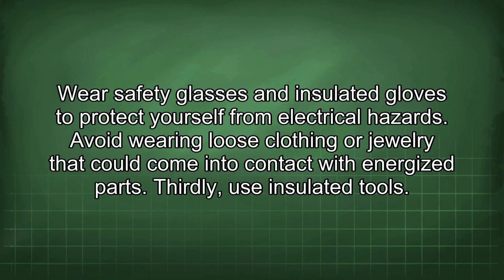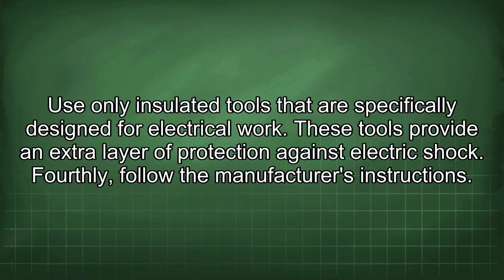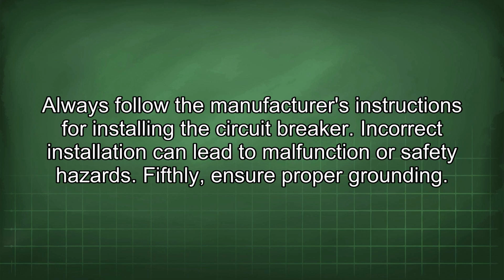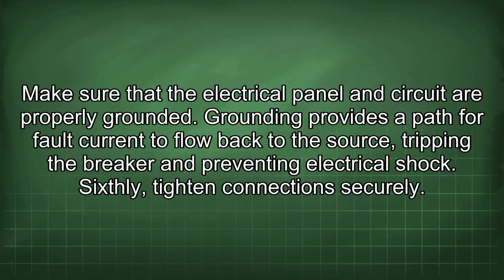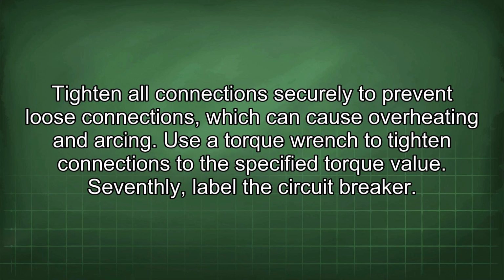Thirdly, use insulated tools. Use only insulated tools that are specifically designed for electrical work. These tools provide an extra layer of protection against electric shock. Fourthly, follow the manufacturer's instructions. Always follow the manufacturer's instructions for installing the circuit breaker. Incorrect installation can lead to malfunction or safety hazards. Fifthly, ensure proper grounding. Make sure that the electrical panel and circuit are properly grounded. Grounding provides a path for fault current to flow back to the source, tripping the breaker and preventing electrical shock. Sixthly, tighten connections securely. Tighten all connections securely to prevent loose connections, which can cause overheating and arcing. Use a torque wrench to tighten connections to the specified torque value.